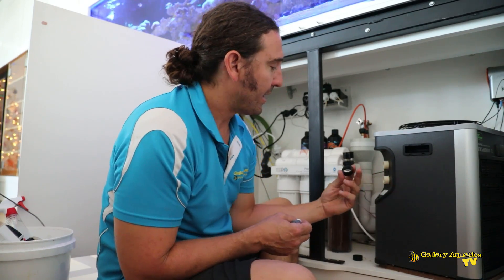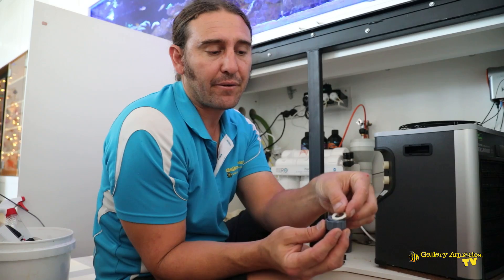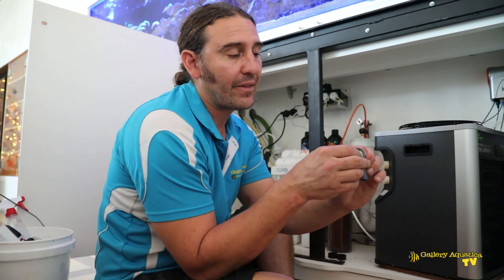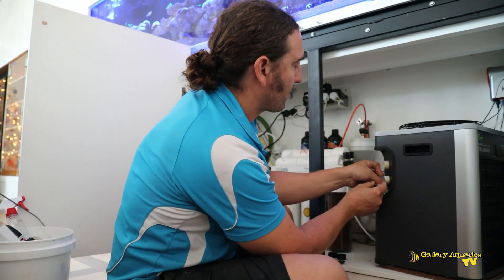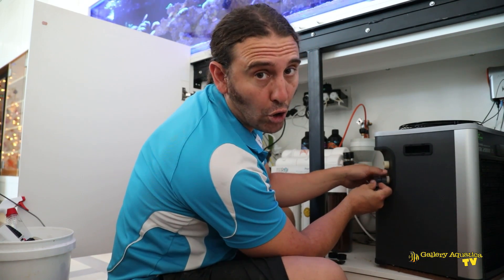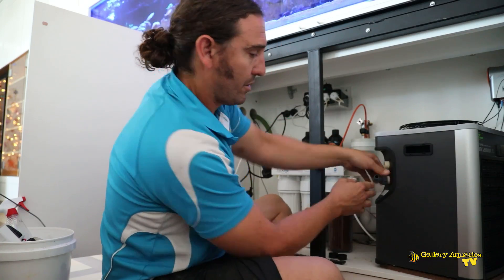If you look closely at the side next to these taps, you've got an intake and an outlet — it says 'in' and 'out'. The water is going to go in through the bottom and come out through the top, so it's important that you get that right. These caps have spare O-rings, so make sure you don't lose those. When positioning the fitting onto the chiller it's very important that seal is in place — hold it with pressure, push the seal in all the way so that when you thread it on you know the seal is in place and hard up against the threaded fitting.